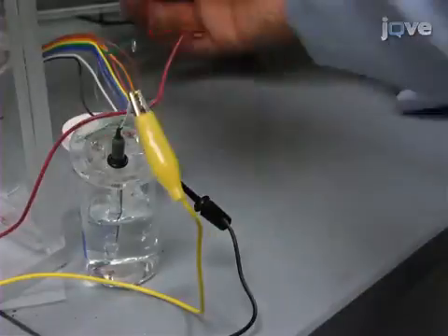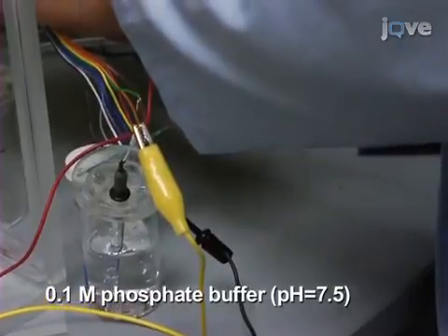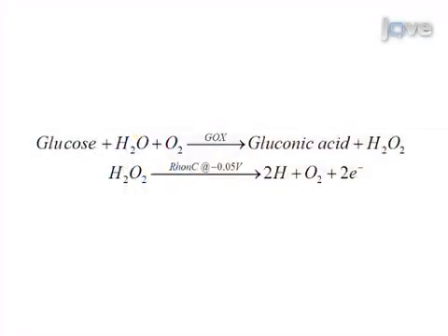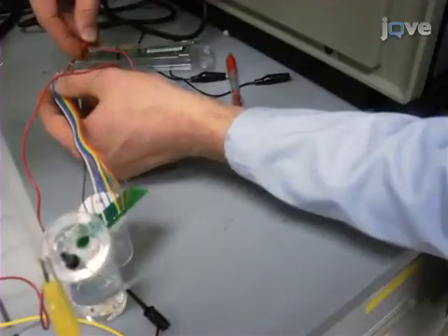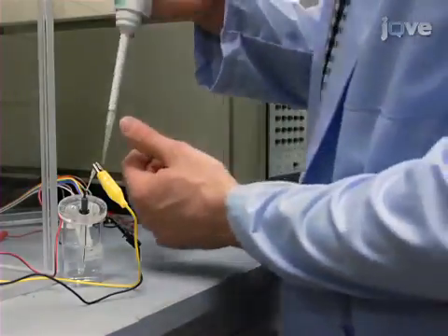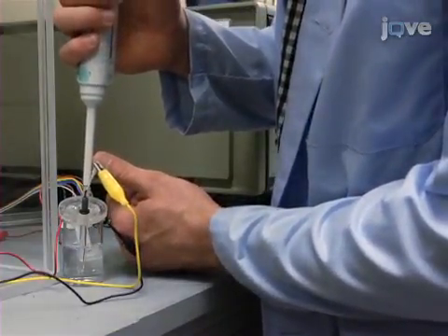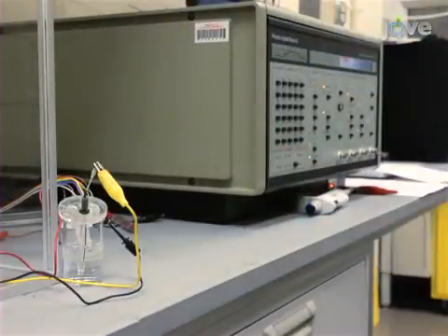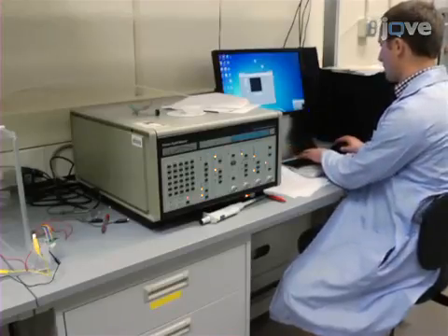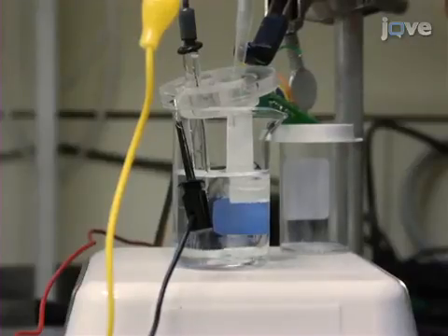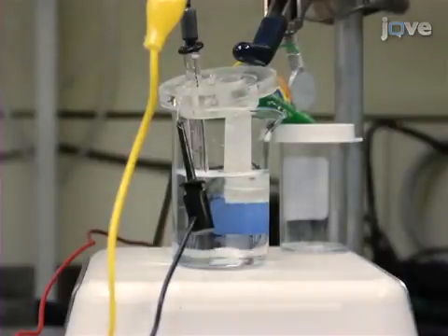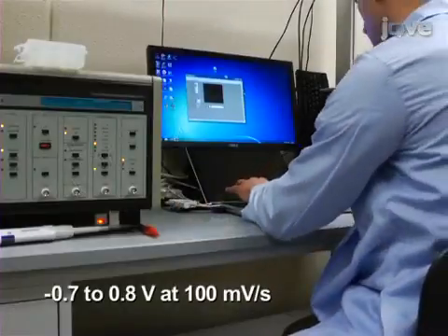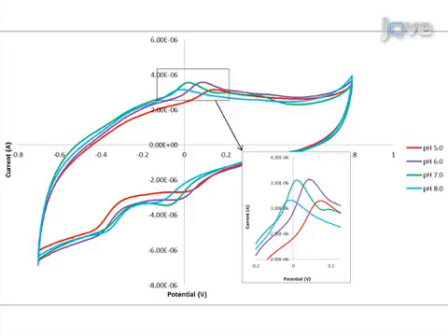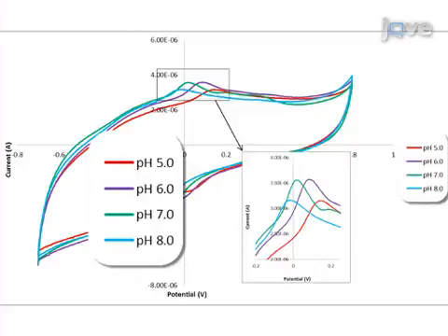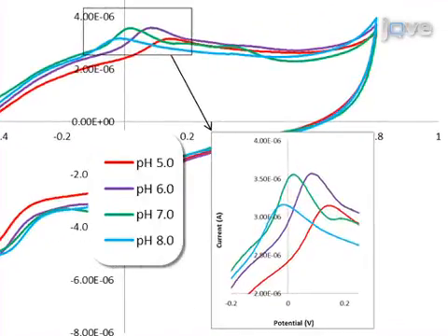To detect lactate, measure the chronoamperometric response of the sensor and record the current after 15 seconds. To detect glucose, measure the chronoamperometric response of the sensor. To create the calibration curves for lactate and glucose sensors, successively add the respective analyte prior to chronoamperometric measurements. Alternatively, perform fixed potential chronoamperometric measurements. While stirring, allow sufficient time in between each analyte addition for current stabilization. To monitor the pH, perform cyclic voltammetric scans and record the positions of the oxidative peak potential values. Create pH calibration curves by measuring the position of the oxidative peak potential in recorded cyclic voltammograms over a series of known pH values.